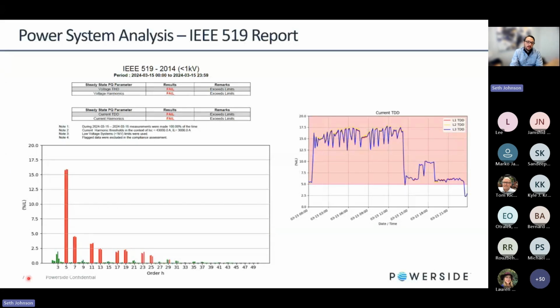You can see here, this is for a very large spectrum of harmonics. So, this is a 6-pulse drive load primarily that we're seeing here. And this is a spectrum you would expect to see, but it was on a very weak power distribution grid. So the effects of the current harmonics on voltage were quite significant. And so, we had to deploy a solution to meet the standards required by the utility power provider.